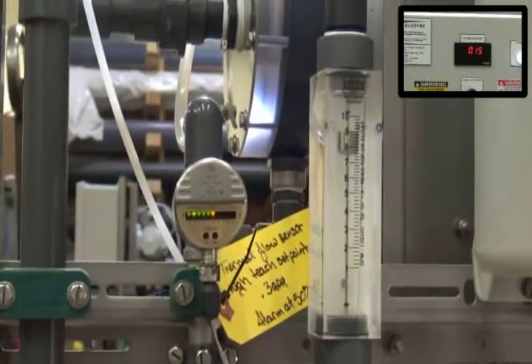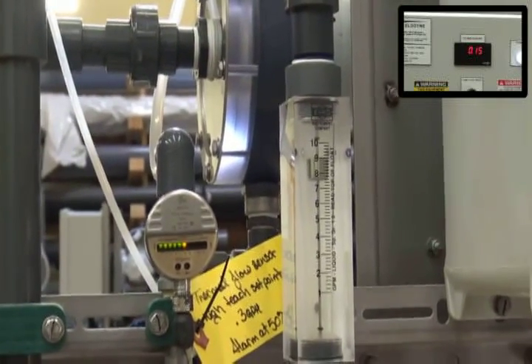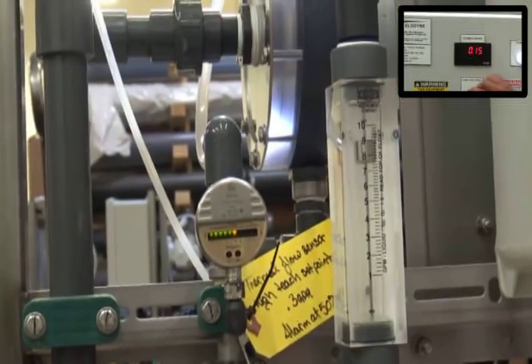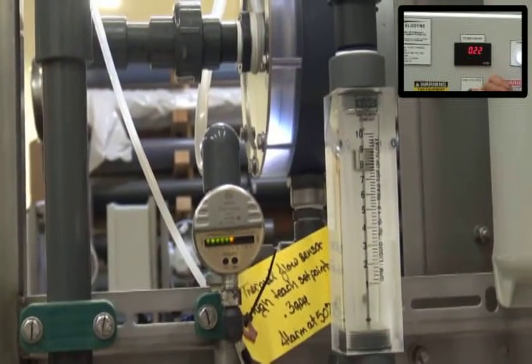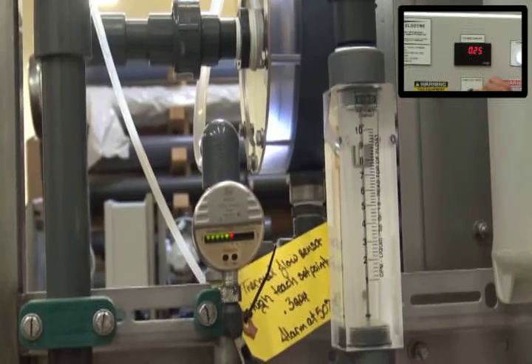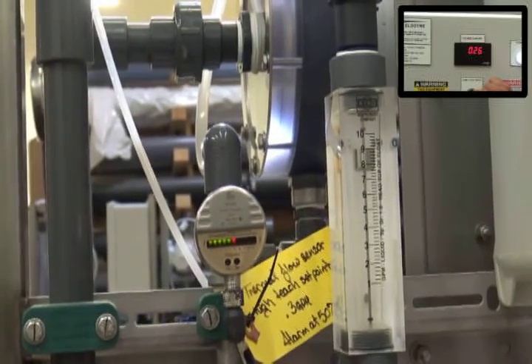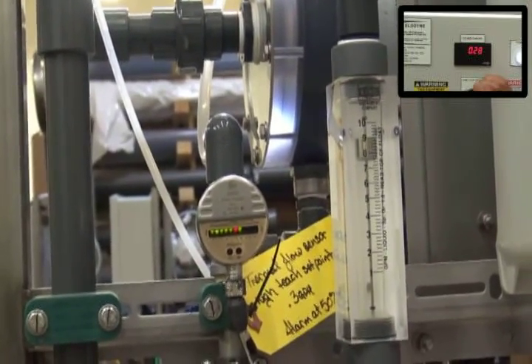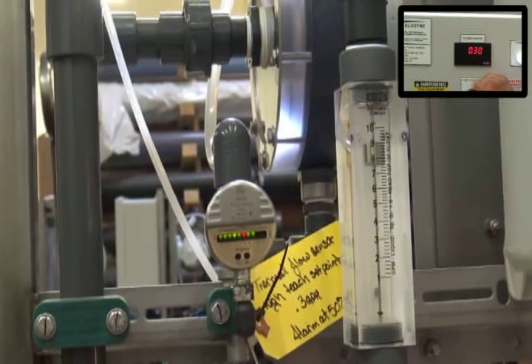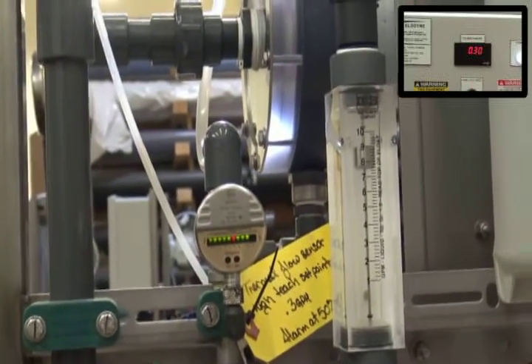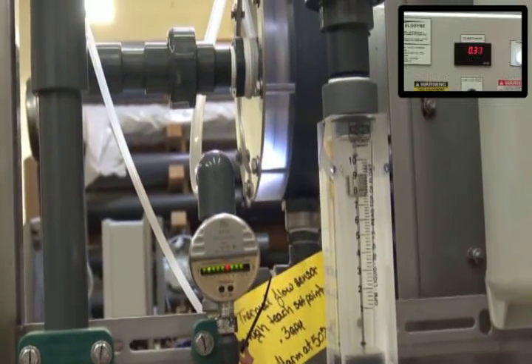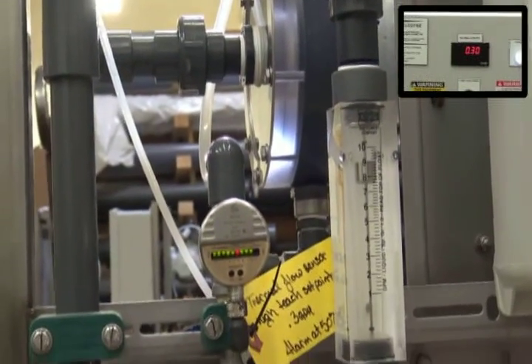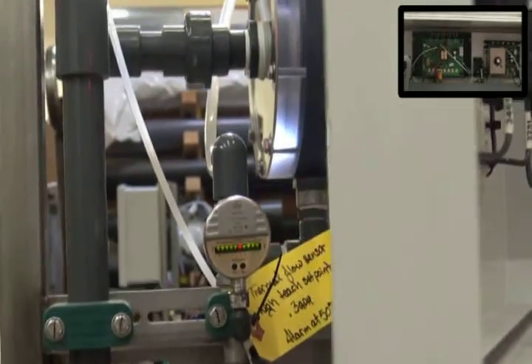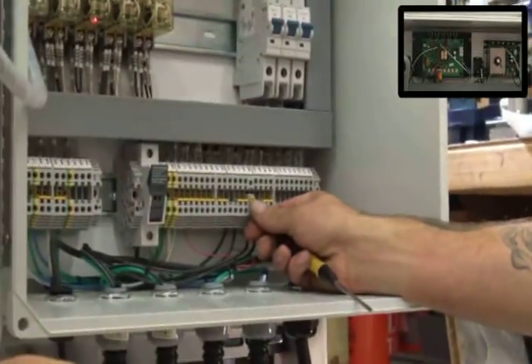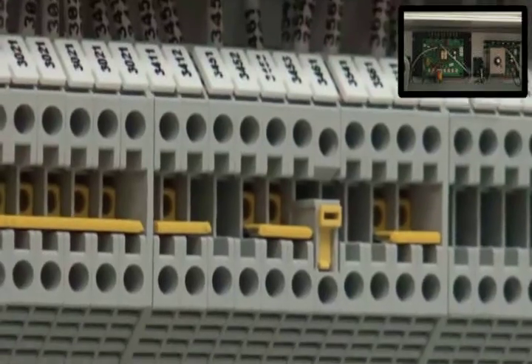Now, after you've got all that done, you can turn your pot back up a little bit, make sure that it's in that running state, so the red light is back on. And then you can either turn the system off or open the panel. All we need to do is we need to put that blade terminal back to that signal's position. So depending on what your process is on electrical panels, if your plant requires you to shut it down before you open it, you can.